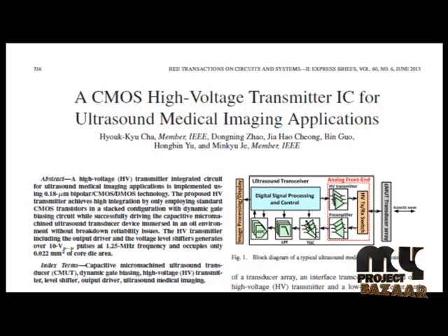The transmitter efficiency is defined as the ratio between the useful acoustic power and the total power dissipated. One of the main issues is the area-hungry high voltage transmitter in the interfacing analog front-end IC. The high voltage transmitter usually utilizes large size high voltage diffused MOS, that means DMOS transistors, to generate high voltage pulse signals to drive the CMUT and produce large acoustic pressure while maintaining reliability to prevent possible device junction breakdown.